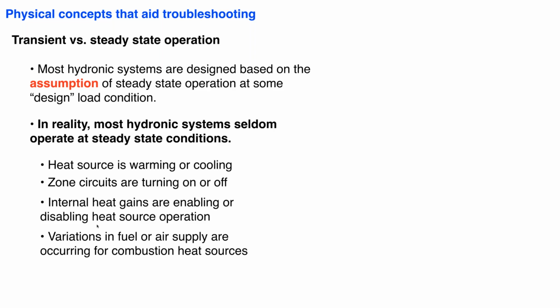That is going to change from, if the system was at steady state and we turn another zone on, we are at least temporarily throwing that system into a transient condition. Internal gains in sunlight, people, lights, appliances, anything like that, even variations in fuel or air supply, air fuel ratio going into the combustion system, that can all have a bearing on the heat output, and hence it could cause conditions to change within the system. So really what we're doing is troubleshooting a moving target rather than a steady target.